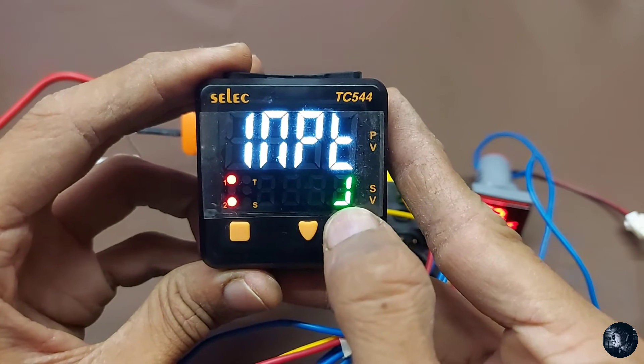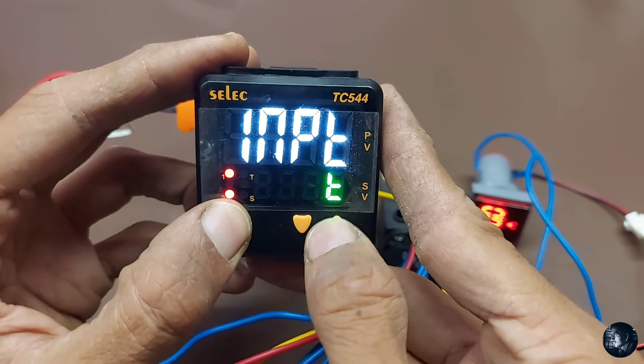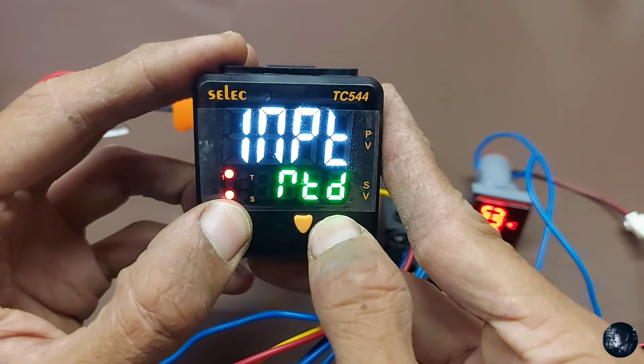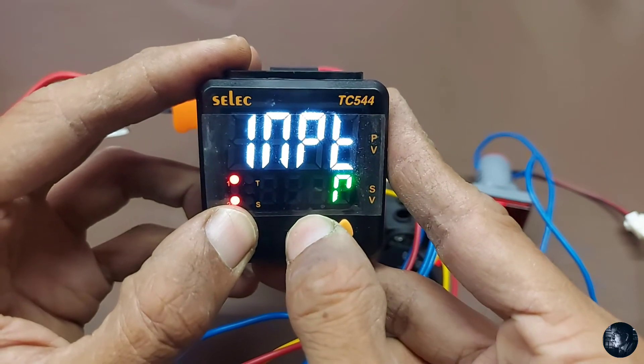For programming the Selec Model TC544, press the down key for three seconds. This enters Group 1 — input selection. Press the select button and while holding it, press the up button to cycle through different selections: J type, K type, T type, S type, and RTD. We have to use K type.